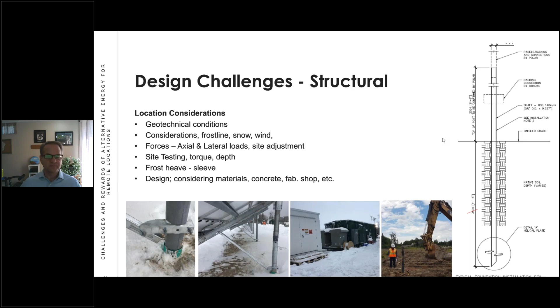It was through this testing that we were able to discover that the soils on the original site plan weren't strong enough to provide the strength needed at reasonable depths. So with some additional testing on site, we shifted the entire site by about 20 meters to the south, where we would find the right soil bearing capacity needed. This testing program helped us find the right location with the soil bearing capacity needed to properly support the solar racking, the e-house, and the battery storage building.